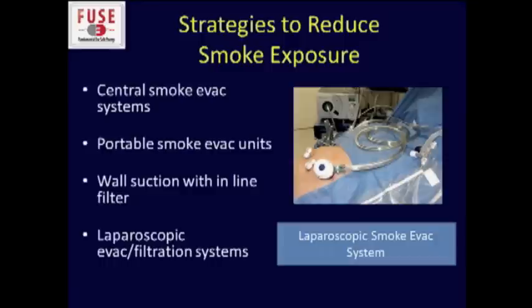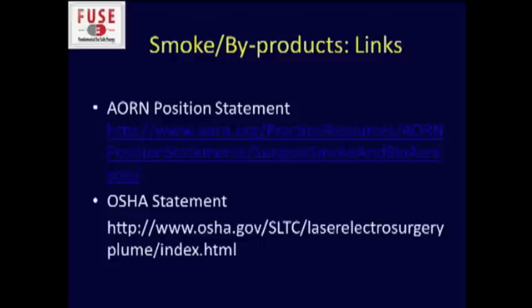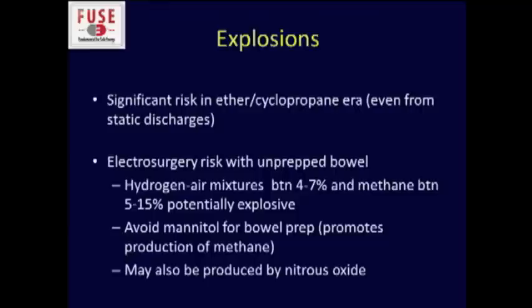OSHA has recommended that smoke evacuation systems be used routinely in the operating room — this is not a mandate, but it is a recommendation, and I think we should use these more frequently. There can be central smoke evac units, portable units, wall suction with inline filter, and specific laparoscopic evacuation and filtration systems. I think eventually this will be mandated anytime we're using any electrosurgical device that's going to generate smoke.